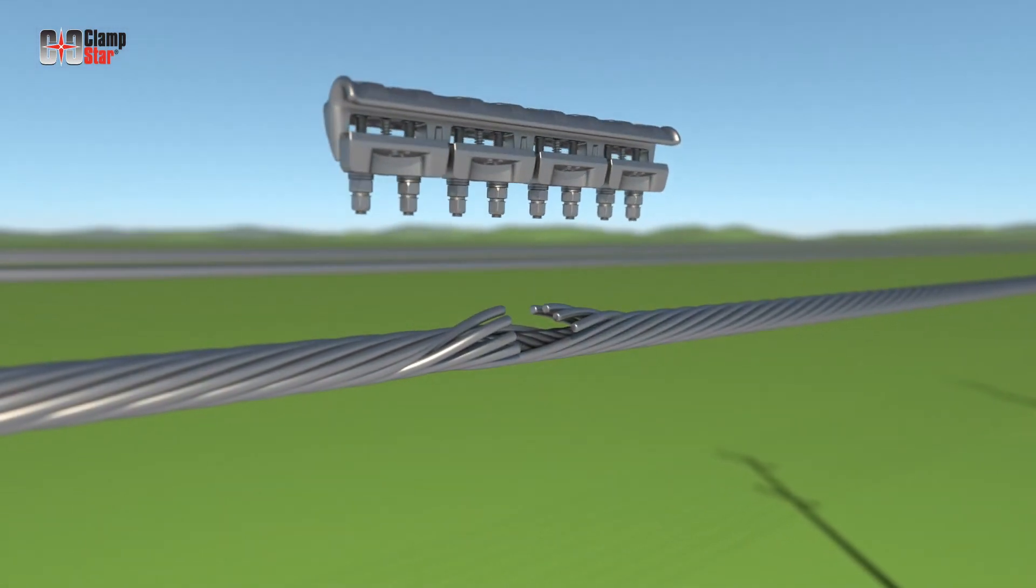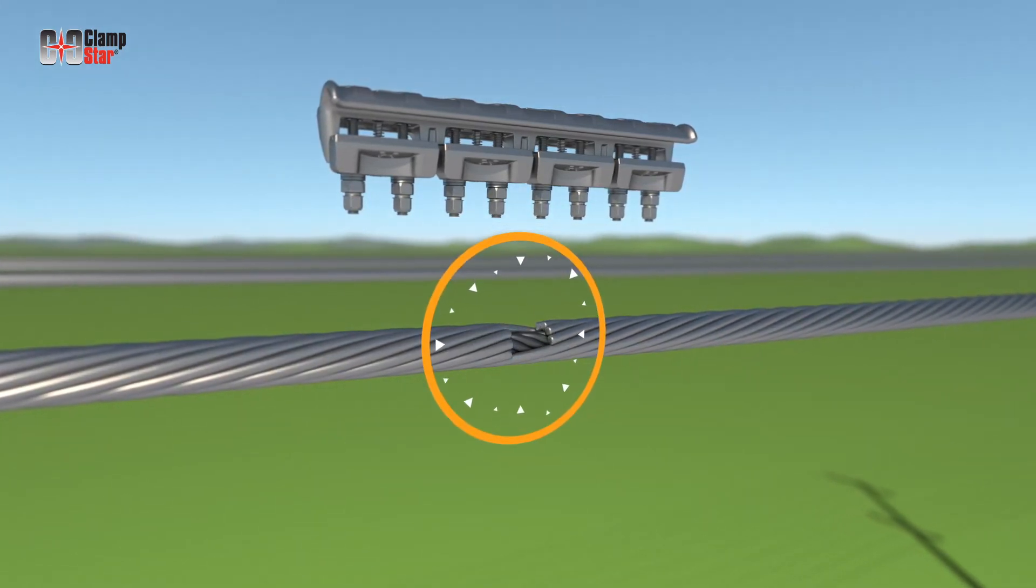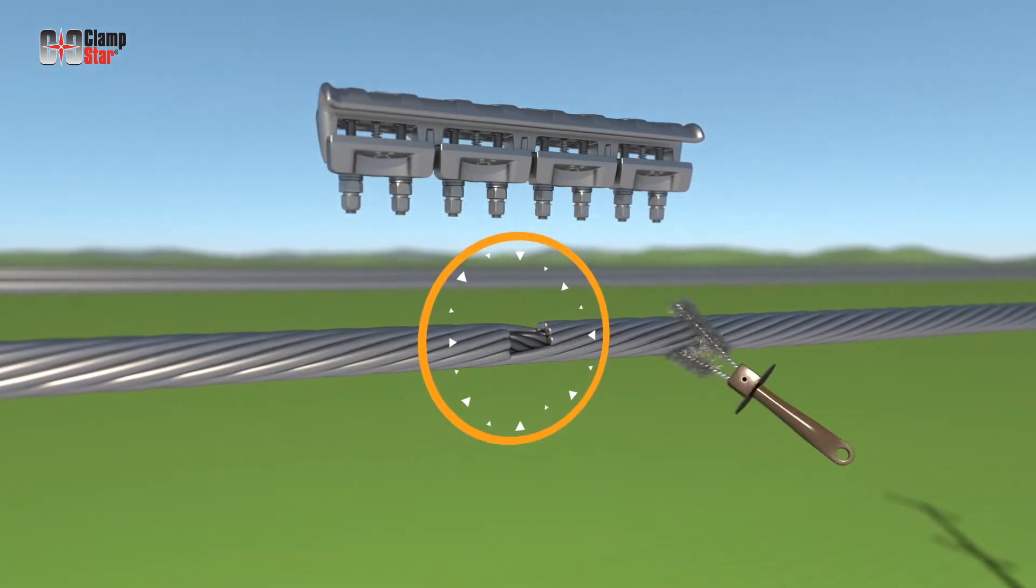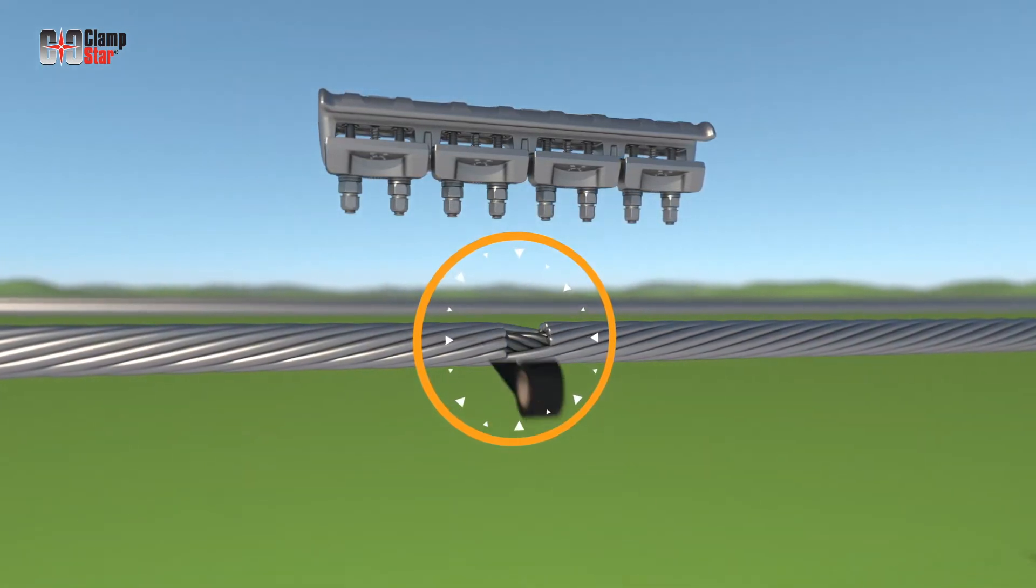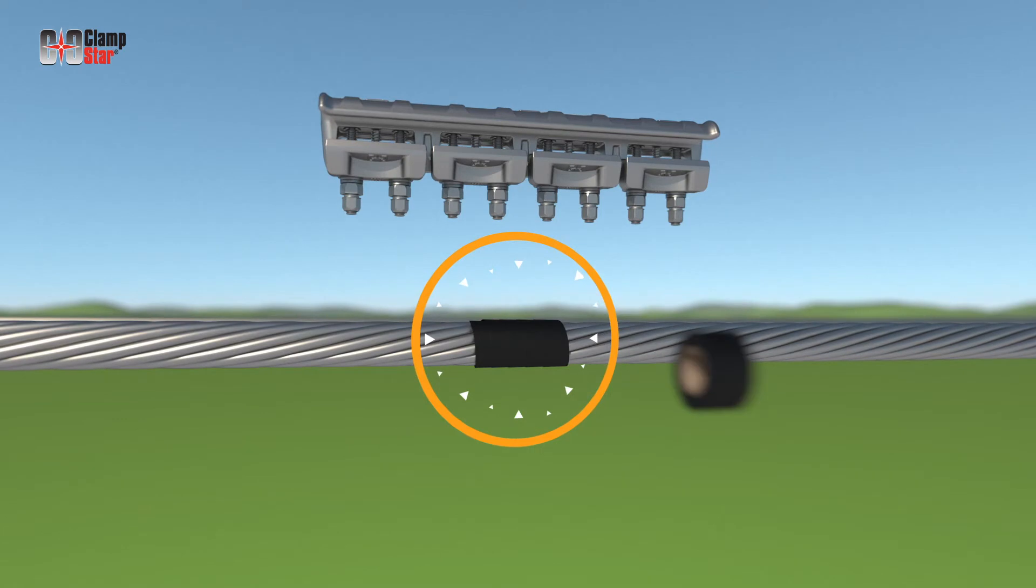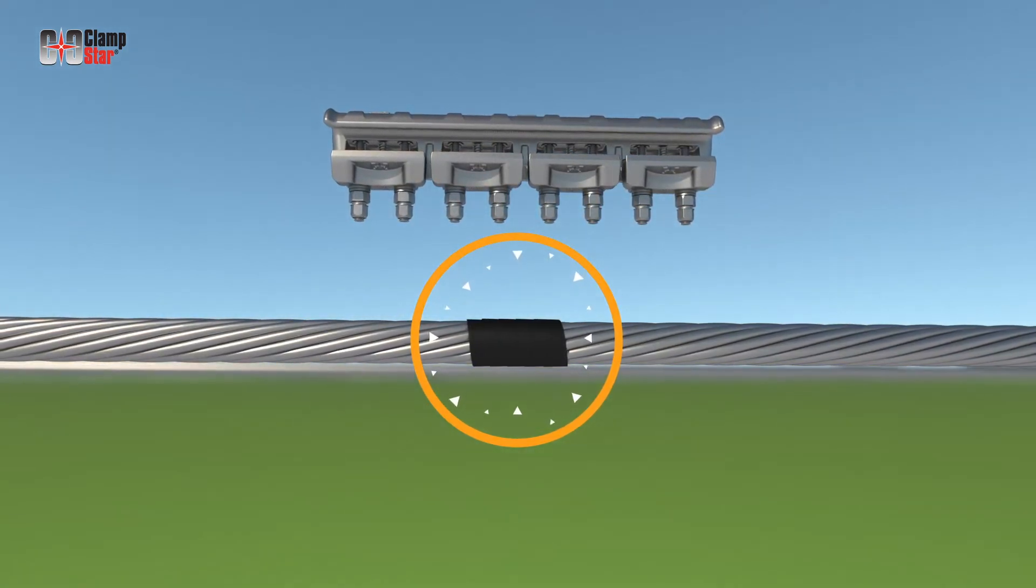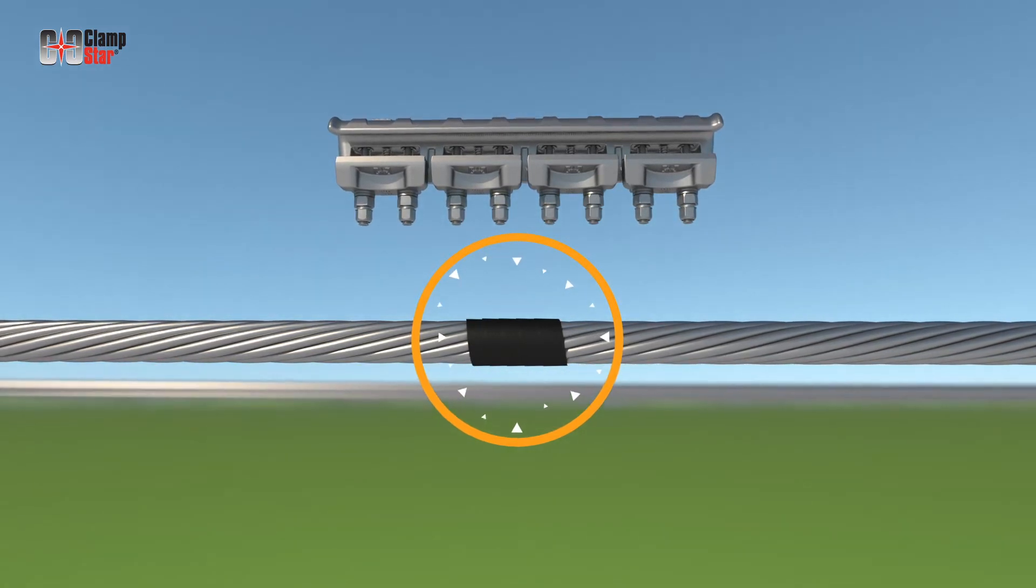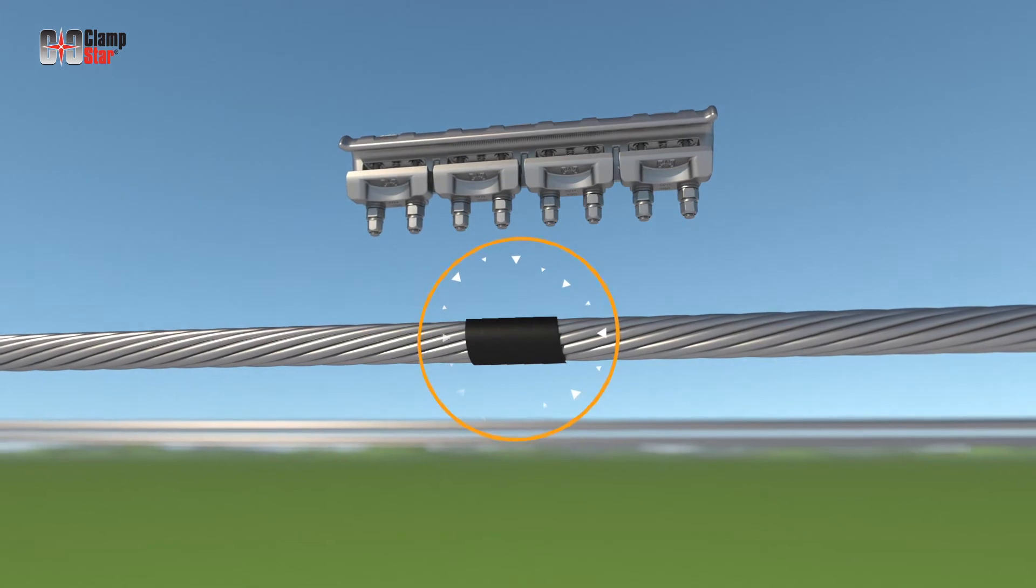Prior to installing the ClampStar, the conductor must be properly prepared by correcting the lay of the wire strands and scratch brushing the area that will be in contact with the ClampStar unit. If necessary, a minimal amount of tape can be used to keep the strands in place. The inhibitor is preloaded from the factory in the conductor grooves of the ClampStar and on the keepers as required. No other inhibitor is to be used.